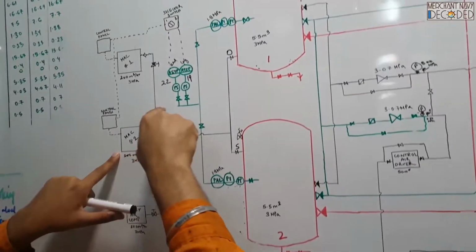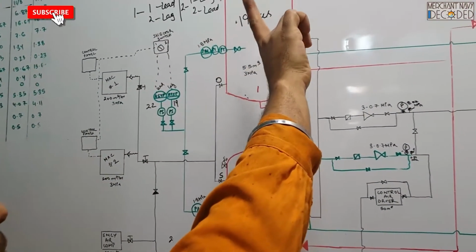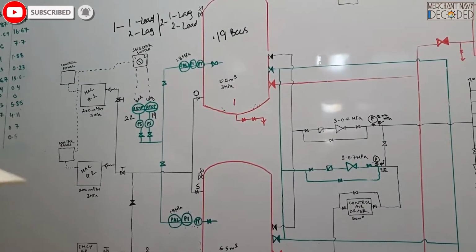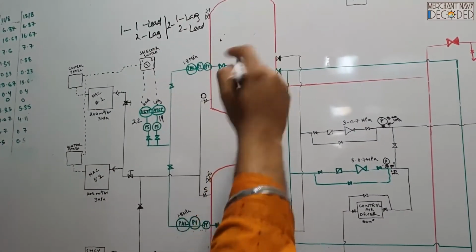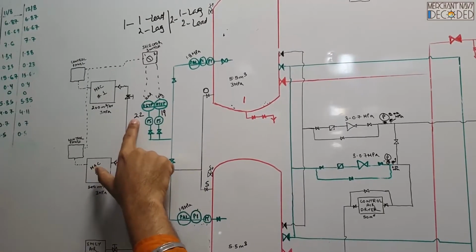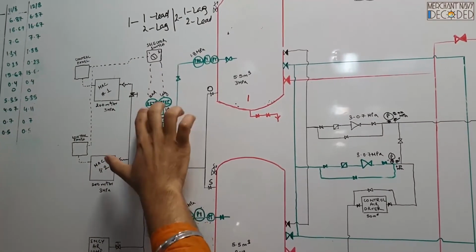So now both the compressors are running and this one is also sending the air, and now my pressure starts increasing more frequently, in a vigorous way. So now this 19 bar starts increasing: 20 bar, 21 bar, 22 bar. Both these compressors are running like that. So guys, this is how my lead and lag pressure switches work.